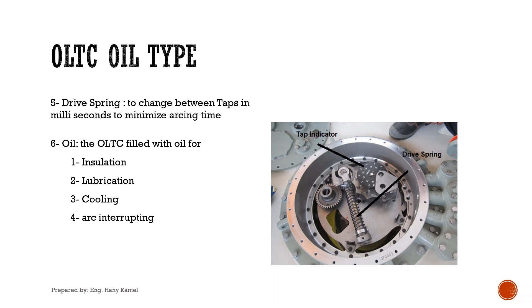Drive spring: as tap changing will happen under loading condition, arcing will happen between the moving contacts and fixed contacts. So we need to minimize the arcing time — thanks to the drive spring, which will be charged then released, shifting the moving contact from one tap to another in a few milliseconds. The tap changer takes a total time to change tap of around 4.5 seconds, but this includes drive spring charging time, plus a few milliseconds for actual tap changing, plus mechanism normalizing time.